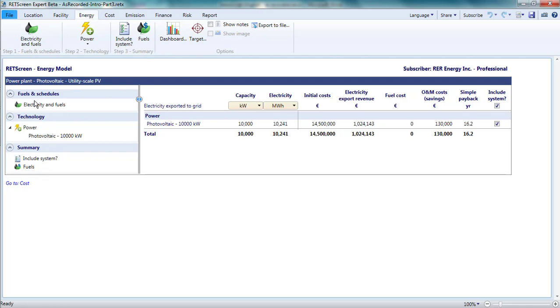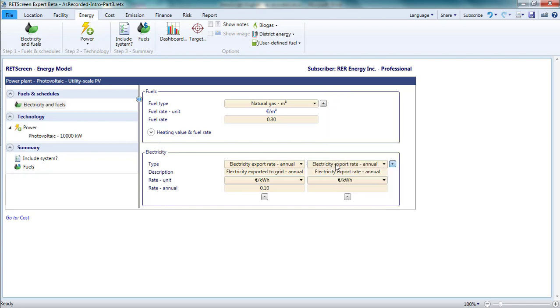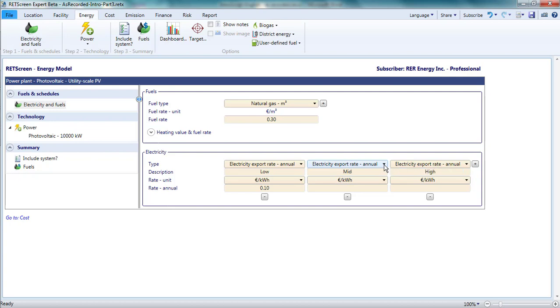I'll start with Electricity and Fuels. A list of fuels and electricity tariffs appears in the right-hand pane of the page. These fuels and electricity tariffs are available for use elsewhere in the analysis, but there is no obligation to use all of them. For example, if I were unsure whether this photovoltaic project would earn 4, 5, or 6 euro cents per kilowatt hour, I could define three electricity tariffs and name them low, mid, and high export tariff. Then, when I'm defining my project later on, I could pick one of these tariffs by name.